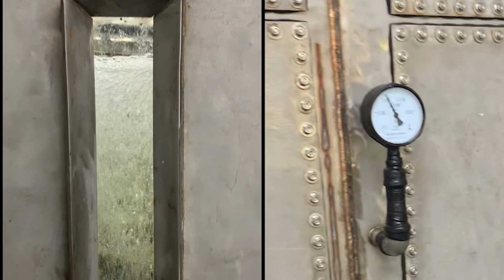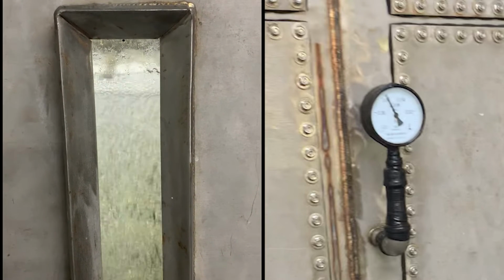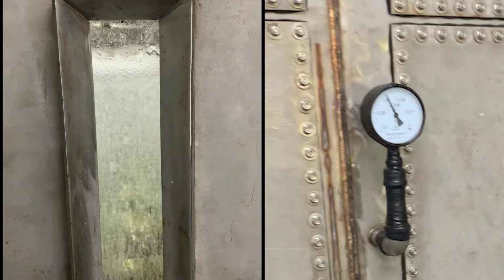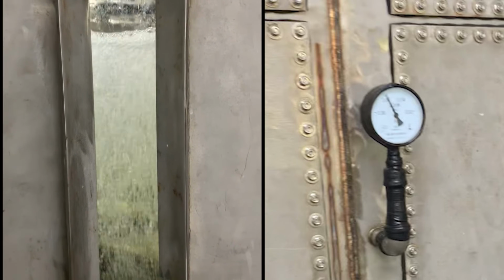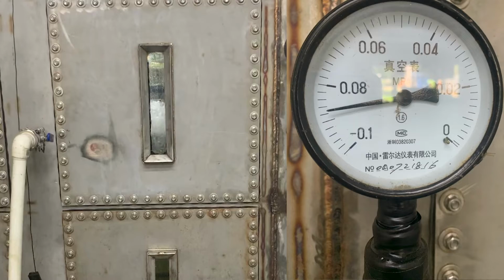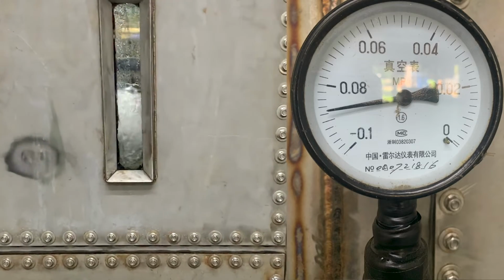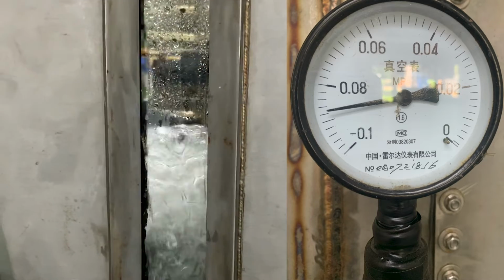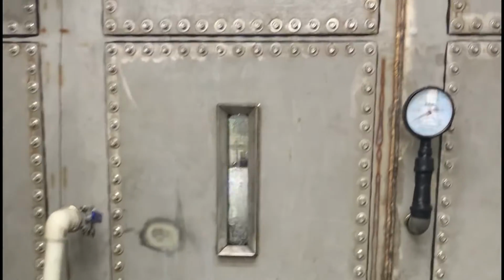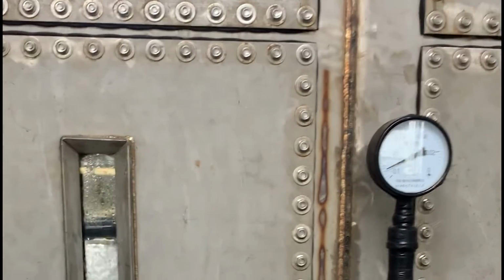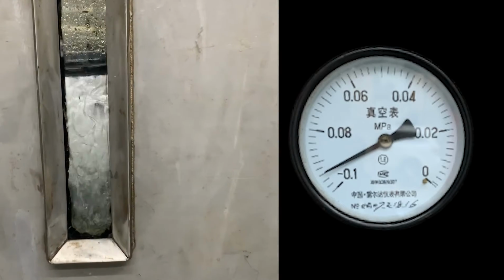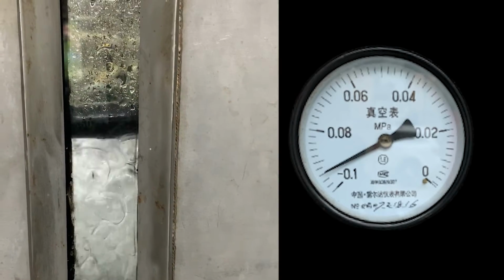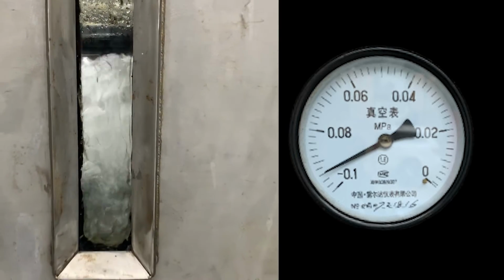Removal of various dissolved gases and other contaminants from the water, including carbon dioxide, purifies the seawater considerably and raises the pH level of the resultant drinking water. As the vacuum level reaches 65 torr, you can begin to see the start of the boiling process. As the pressure drops further, down to 60 torr in this case, the boiling intensifies further. Now at 55 torr and below, the target boiling point is reached. At this stage, the condensation equipment kicks into gear, which allows the freshwater production to begin.